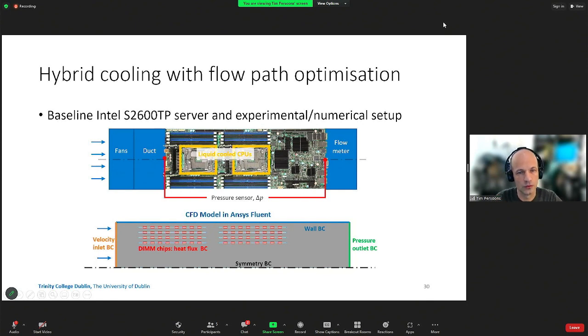So we did remove the heat sinks here from the server. So the assumption is once you liquid cool the CPUs, that frees up a lot of empty space in the middle of the server. And so if you don't do anything else, and you just have the fans pushing air through the system, most of the air will just bypass the DIMM modules and go through the middle basically, which is now empty space because the CPUs are liquid cooled by very small cold plates that don't really exhibit a lot of resistance for the airflow. So, logically, what you want to do is to have some baffles here so that you redirect the airflow to go mostly through the DIMM modules. And so that's what this research was all about, finding the optimum shape of the baffles inside to maximize waste heat recovery potential.